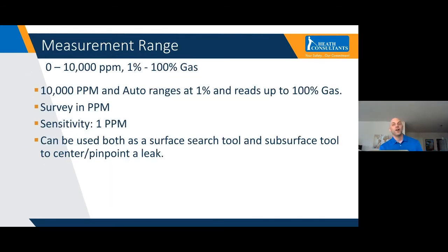On the DPIR, there are two ranges. I mentioned you can do the leak survey at low level sensitivity, and it goes up to the high end. Your two scales are 0 to 10,000 parts per million, which is 1% gas, and then 1% gas up to 100% gas. And you as a user don't need to worry about switching anything.